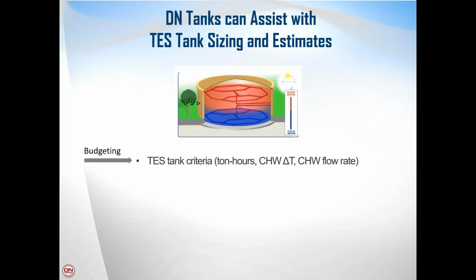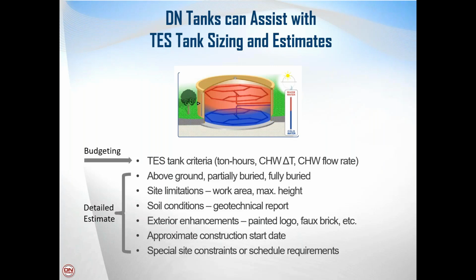So if you're looking at projects and considering thermal storage, or the owner would like to look at projects, we can help with budgeting for sizing a thermal storage tank and estimating the cost. And for doing that, all we need is this information. How many ton hours and what is that chilled water delta T of the system? And with that information, we can provide a tank size and budget estimate for you and for that owner.